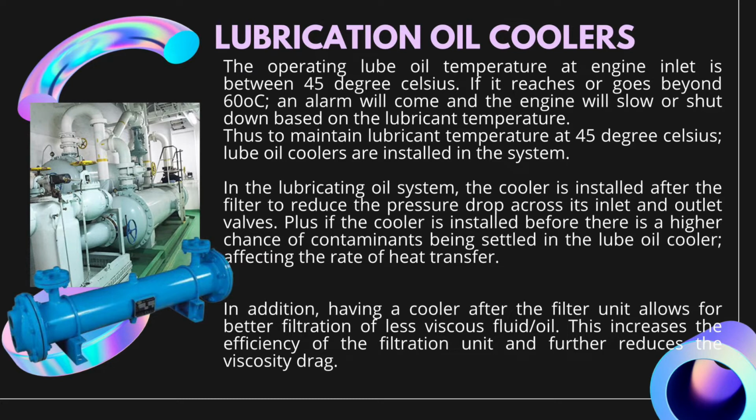Plus, if the cooler is installed before, there is a higher chance of contaminants being settled in the lube oil cooler, affecting the rate of the heat transfer. In addition, having a cooler after the filter unit allows for better filtration of the less viscous fluid or oil. This increases the efficiency of the filtration unit and further reduces the viscosity drag.